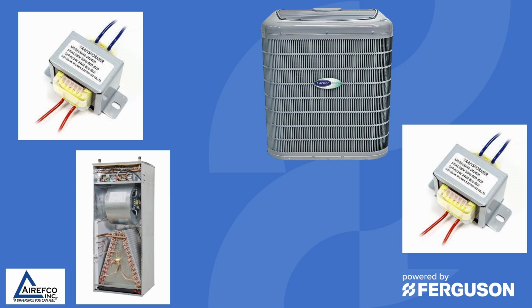So when wiring up indoor and outdoor units, make sure that you check the installation instructions and make sure that if the indoor and outdoor does have a transformer, that you keep them separate.